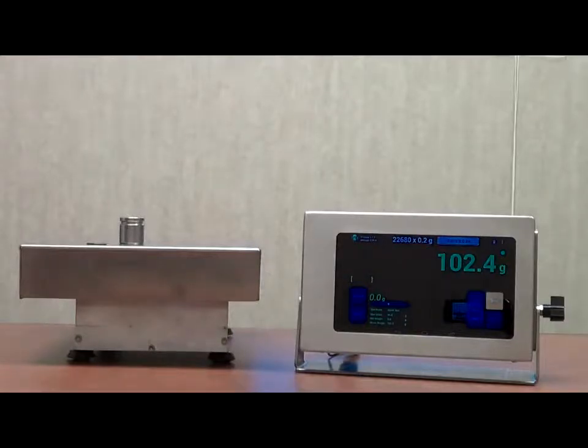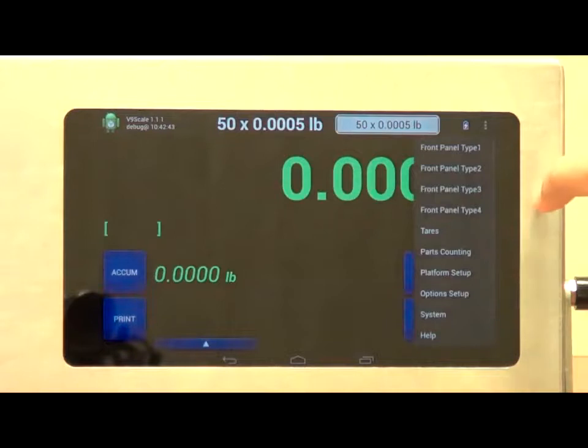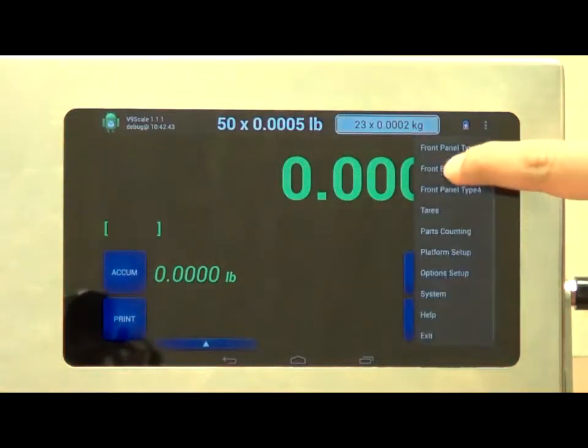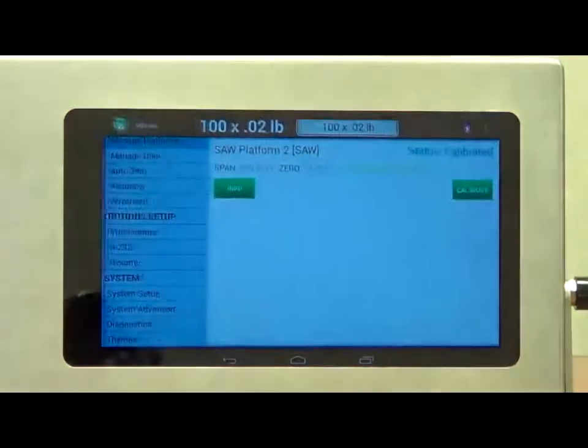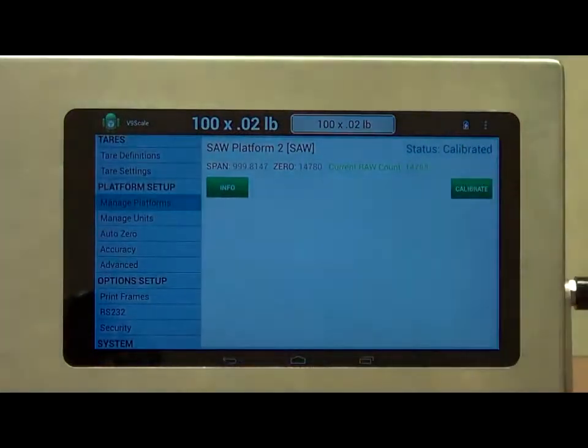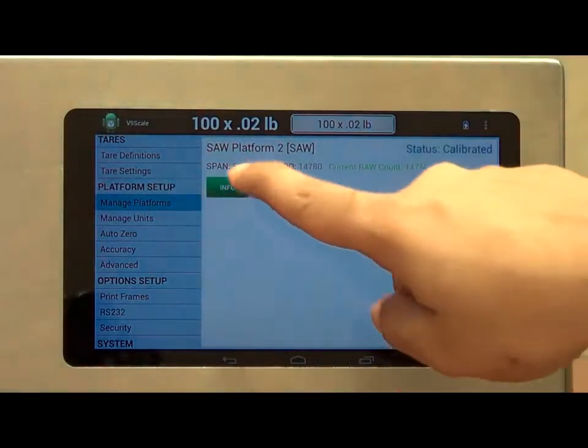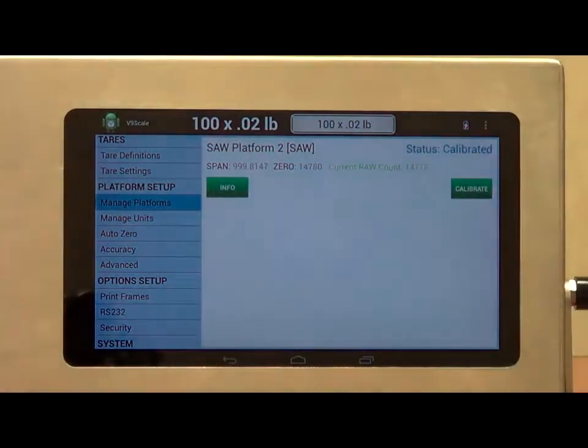We'll have someone else here demonstrate some of the functions. Let's look at the settings on the scale. I can easily access that by pressing the top right button on the screen. We are going to look at the platform setup. In this screen, we can look at the status of the current platform. We see the calibrated span, the calibrated zero, and the current raw count. We know the scale is working fine if you see this raw count moving.